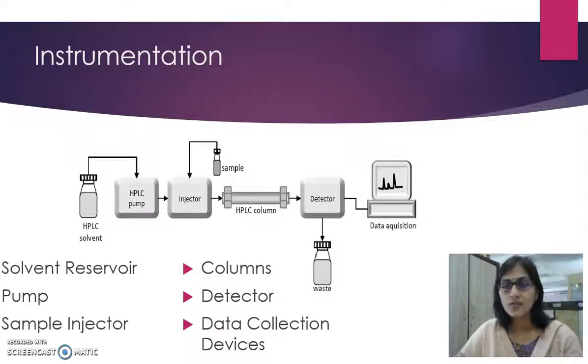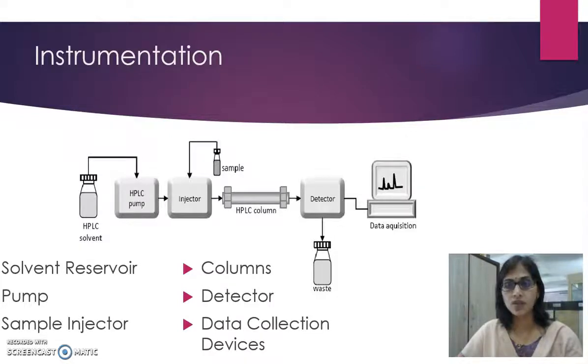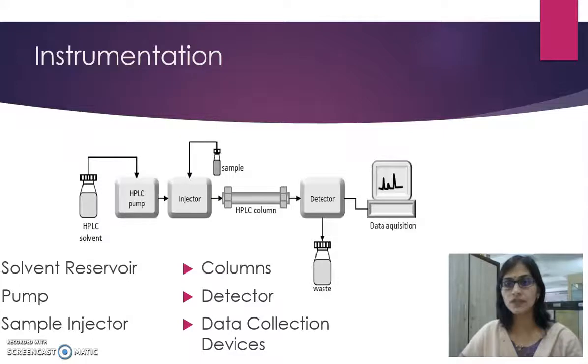Columns are usually made of polished stainless steel and are between 10 to 30 cm long and have an internal diameter of between 4 and 5 mm. They are commonly filled with a stationary phase with a particle size of 3 to 10 micrometers.